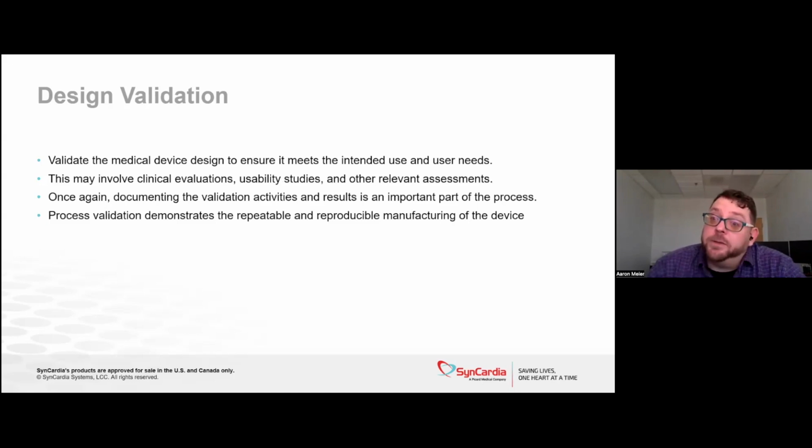The next phase of the process is design validation. Did I build what the customer actually needs? This is where we go back to our customer requirements and we validate that we've actually met them with our design. The customer requirement might be something like it's fully implantable. The driver works in a backpack, right? These are higher level requirements on what a customer needs, where the customer is going to use it, and how they're going to use it, right?